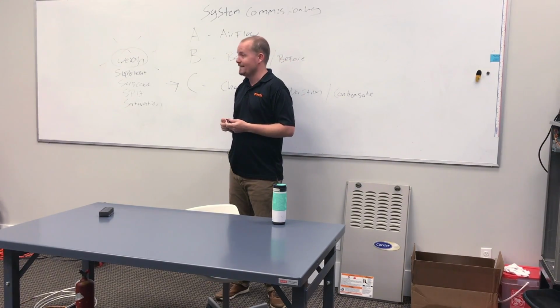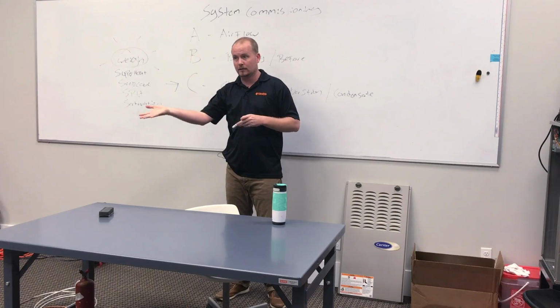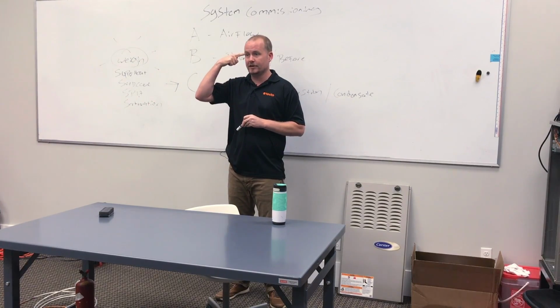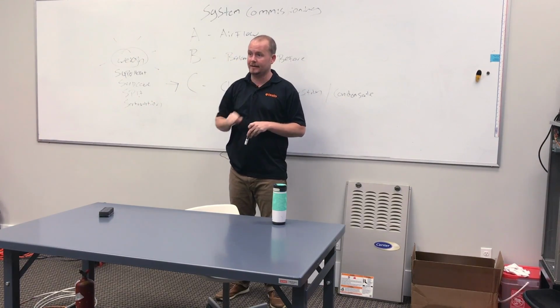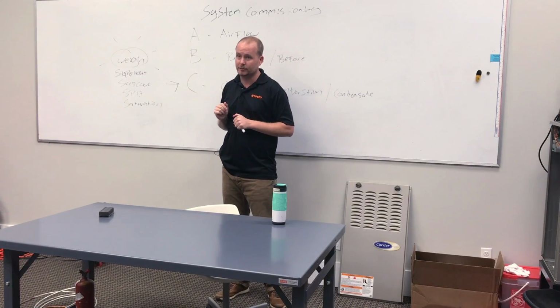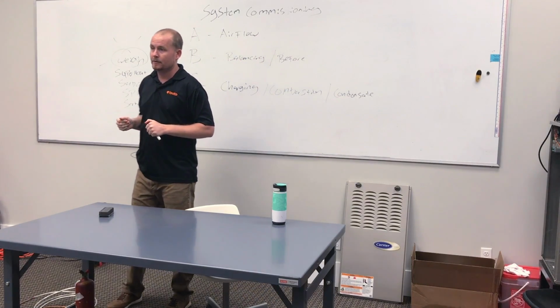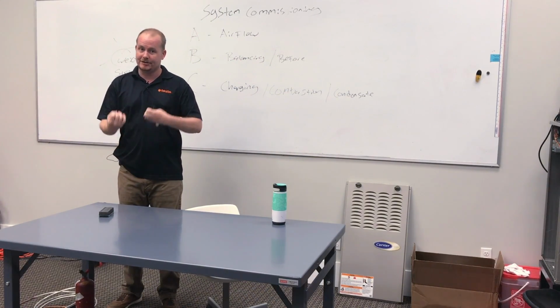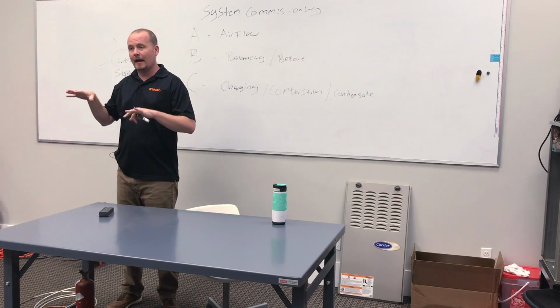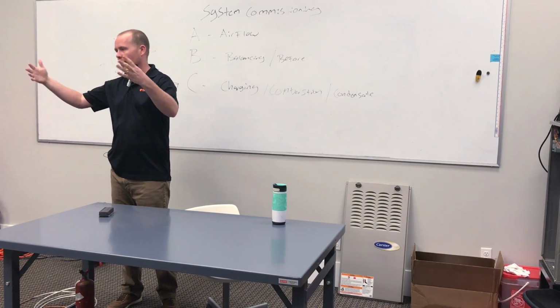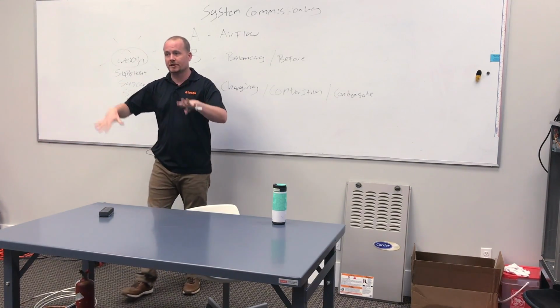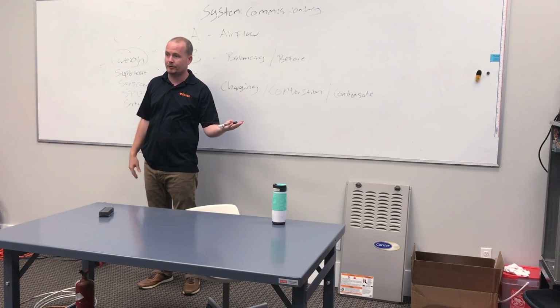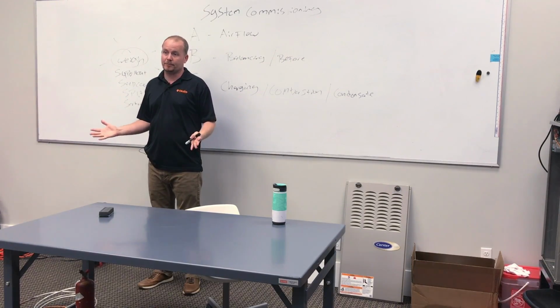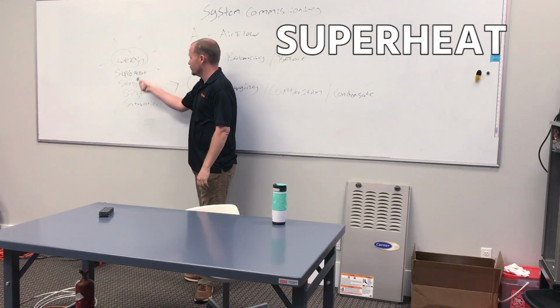When you say my evaporator temperature is blah, that's much clearer, because now you can envision your evaporator being that temperature, and that's pretty darn close to what it's going to be. When you say condensing temperature, you can imagine your condenser is that temperature. That makes it easier to do what I've shown you in the 5 pillars, which is compare those two temperatures to indoor and outdoor temperatures in order to anticipate what your pressures ought to be, and then check your superheat and subcool.